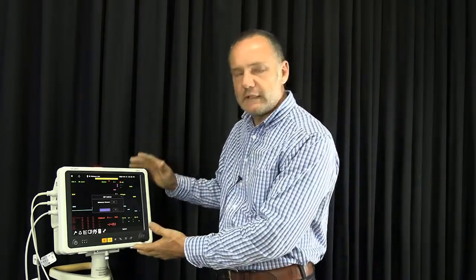Now, what the pressure relief test is, what a patient monitor does is it has a first stop in pressure. So when I press the start button, in normally an adult mode, it will probably go up to about 140 or 160 millimeters of mercury. Then stop, then wait to see if it measures a pulse. If not, it will continue to a higher pressure. And so it will keep on increasing until it finds a point where it blocks the pulse of the patient. Now, in order to safeguard the patient, these monitors have an overpressure point, normally around anything from 280 to about 350 millimeters of mercury, where the monitor will say, up to here, no more, open the valve, release the pressure.